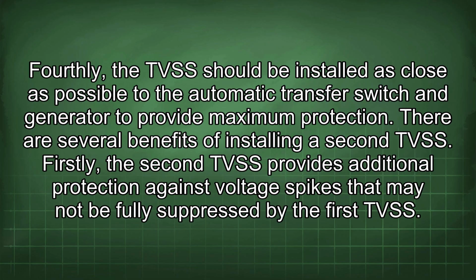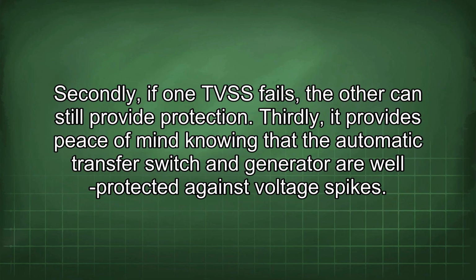There are several benefits of installing a second TVSS. Firstly, the second TVSS provides additional protection against voltage spikes that may not be fully suppressed by the first TVSS. Secondly, if one TVSS fails, the other can still provide protection. Thirdly, it provides peace of mind knowing that the automatic transfer switch and generator are well protected against voltage spikes.